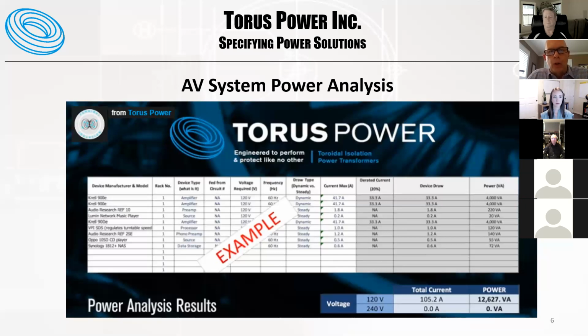The second reason is that you can also use a balanced transformer, which we do in our 240 volt units, to eliminate additional noise present on the voltage line. We use a balanced input on our transformers - we take the 240 input, balance that on the input side, and then the transformer still does the noise filtering through our NBT noise filtering to eliminate even more noise present on the voltage line. It's just, I think, a best practice to use a step-down transformer. It's going to be more reliable, and a better starting point for your AV system, giving you more capability and a bit more noise reduction than a 120 volt transformer.